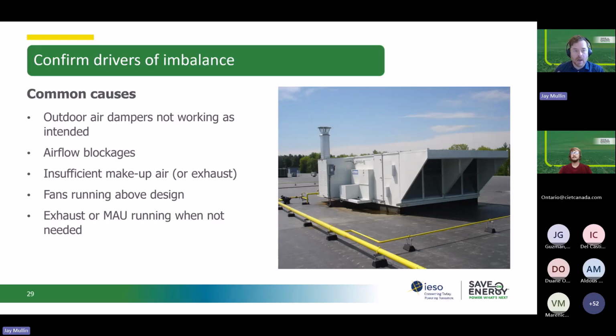So common causes of this are, the outdoor air dampers aren't working as intended. There might be airflow blockages, clogged filters, other things restricting airflow. There might just be insufficient makeup air or exhaust happening. As I mentioned, things change in facilities, and even if it was balanced at design, as equipment was added or removed, it may no longer be balanced in that way.